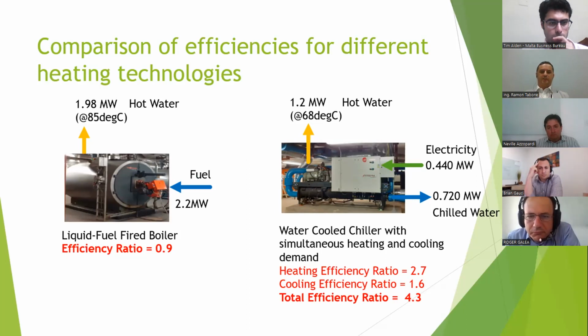So we are inputting 2.2 megawatts of fuel into the boiler. And I have to say that these boilers are very efficient. They have an efficiency of at least 90%. You can get older boilers that are not as efficient as these. But anyway, we're inputting 2.2 megawatts of fuel, and we're getting 1.98 megawatts in the hot water. And that's an efficiency of 90% or 0.9.